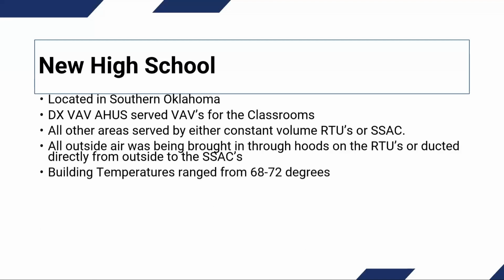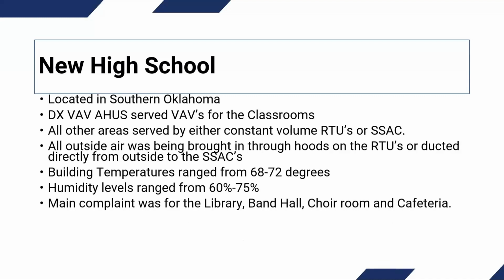Again, the temperatures did range in this building between 68 and 72 degrees. Our humidity levels ranged between 60 and 75 when we first got there. And the main complaint in this building was the library, band hall, choir room, and cafeteria. So the main complaint was in the areas that had the large RTUs that were constant volume.